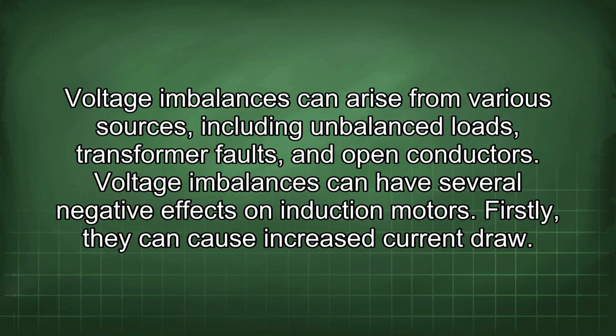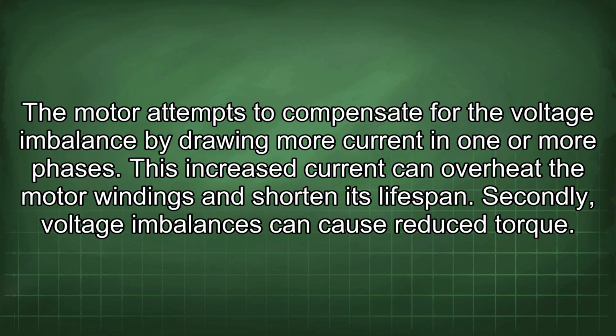Voltage imbalances can have several negative effects on induction motors. Firstly, they can cause increased current draw. The motor attempts to compensate for the voltage imbalance by drawing more current in one or more phases. This increased current can overheat the motor windings and shorten its lifespan.